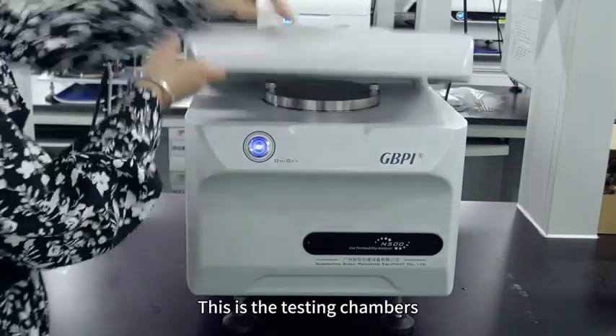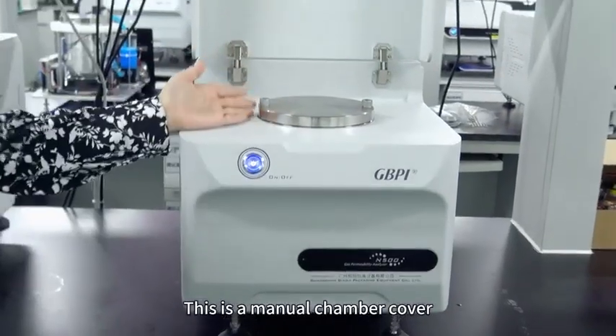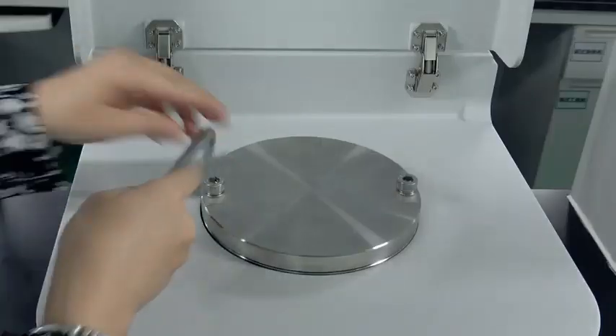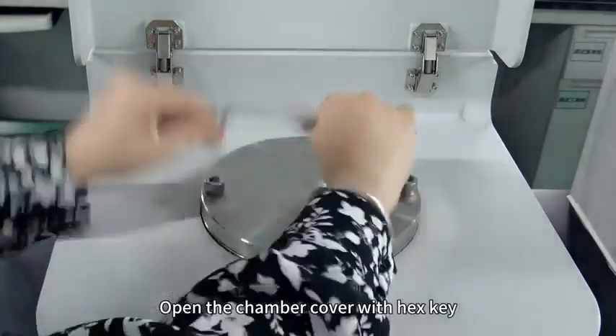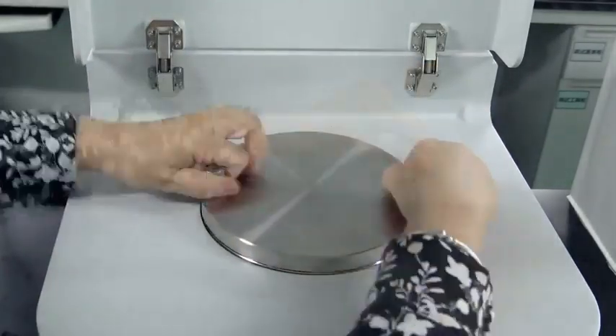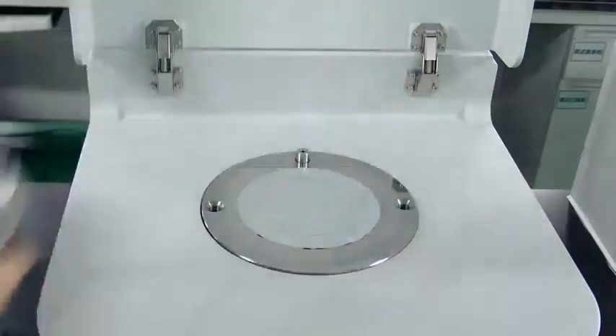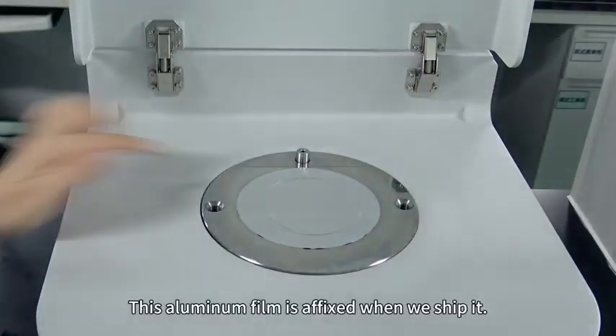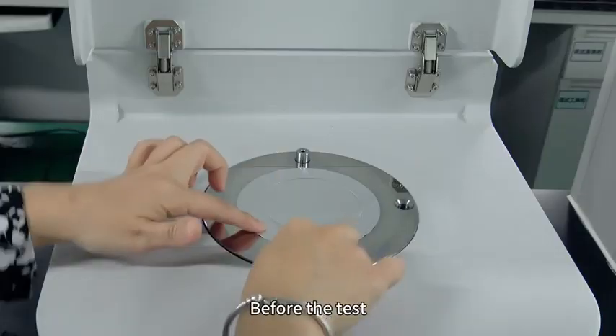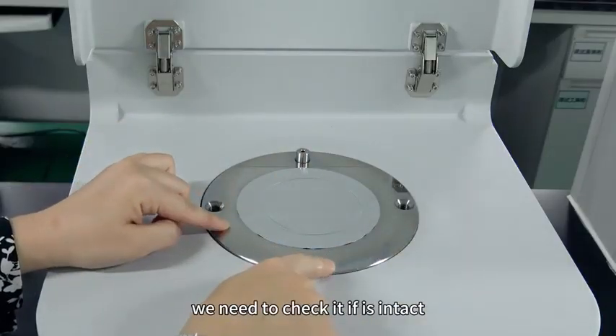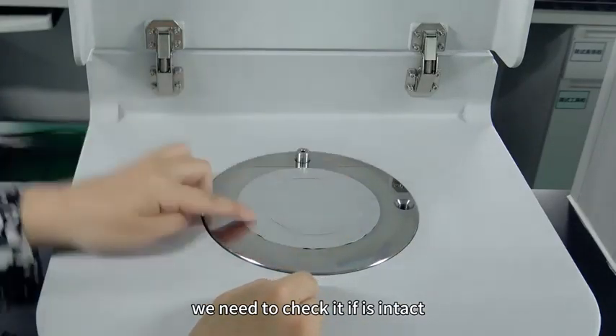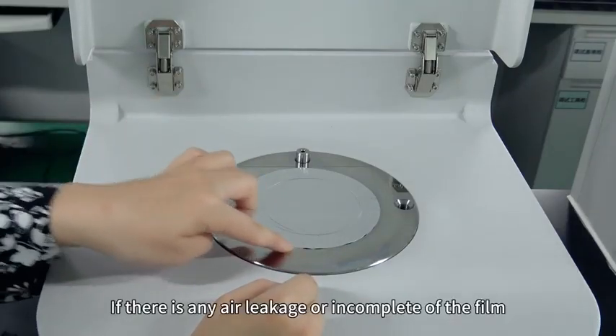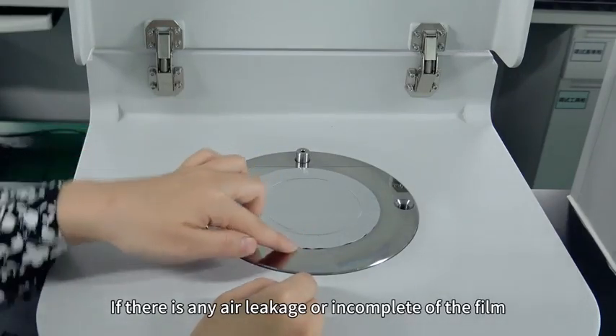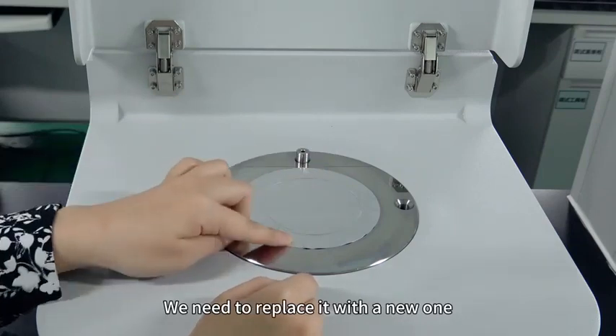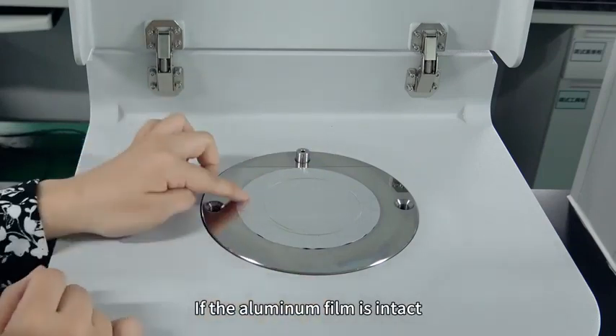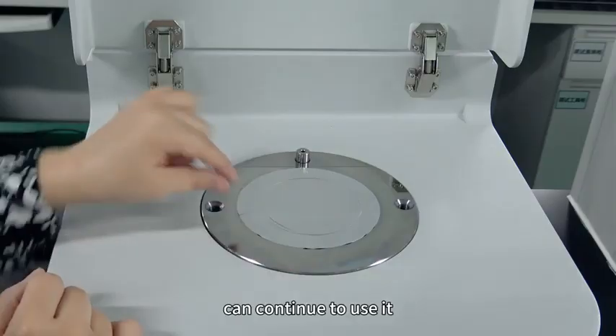This is the testing chamber. This is a manual chamber cover. Open the chamber cover with a hex key. This aluminum film is affixed when we ship it. Before the test, we need to check whether it is intact. If there is any air leakage or the film is incomplete, we need to replace it with a new one. If the aluminum film is intact, we can continue to use it.